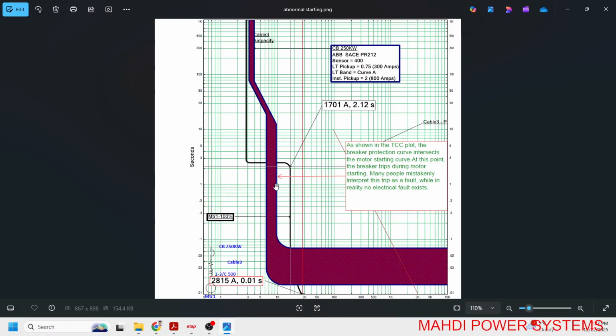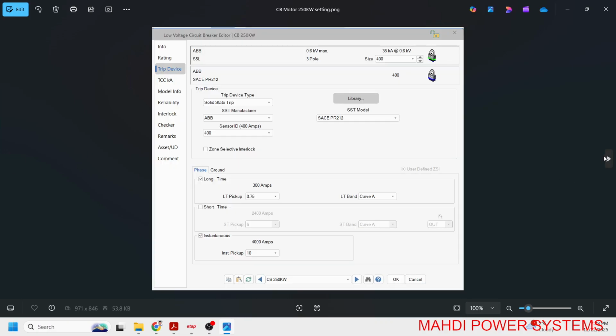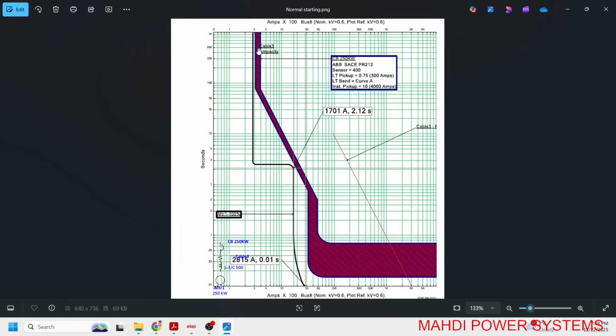Based on field experience, I've seen many cases where electricians assumed a short circuit occurred. In reality, the motor had simply entered the starting region, and that's why the circuit breakers tripped. This is exactly why understanding motor starting behavior is critical before setting any protection. Let's see the correct one. This is the curve of the circuit breaker. As you can see, it does not intersect the TCC of the motors, and this is the correct one.